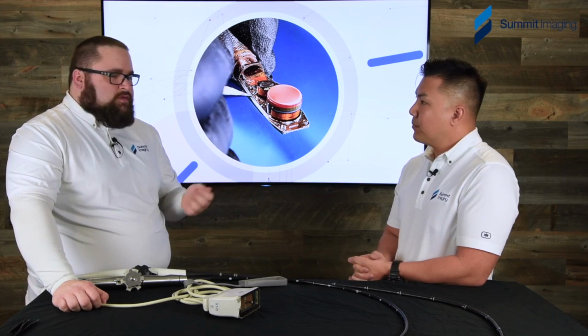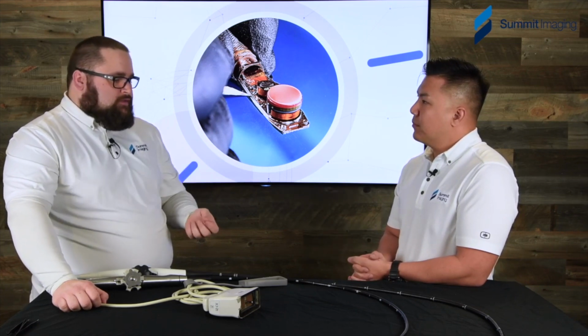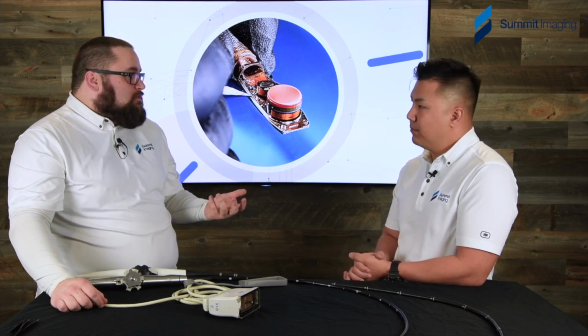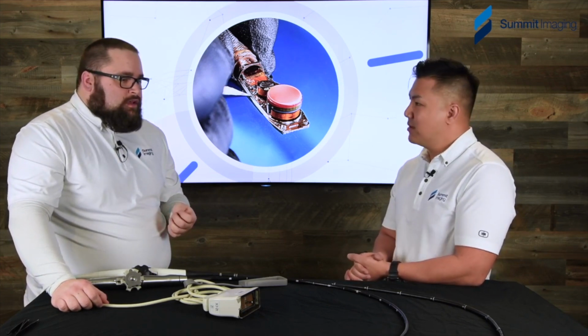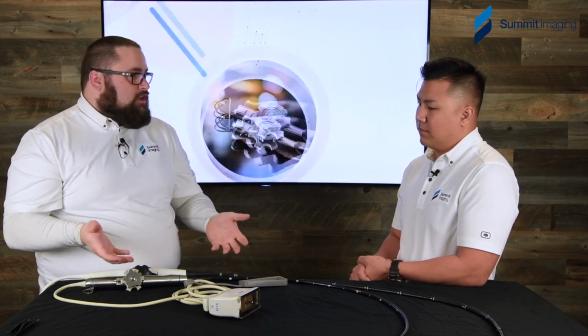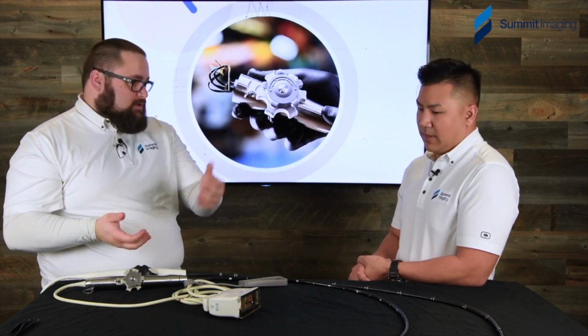Yeah, like I said, with maintenance, a lot of people think these transducers should last forever. You're dipping them in acid every day. They live harsh lives. So yes, the internals should last a very long time. Your bending rubber is going to deteriorate over some time, just like our foggy lens on our other probe, you're going to see this stuff build up. It's never going to be perfect, but if you can just have those maintenance occurrences instead of a critical failure or a full rebuild, or worse, it's just not repairable, you can avoid a lot of that cost and extend the life of this transducer, which is the idea, the cost of ownership, right?